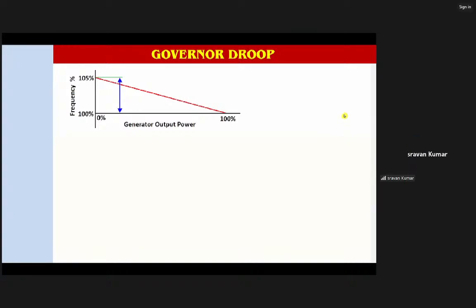Droop is basically this: whenever the machine unloads from full load to 0, maybe because of the opening of the generator circuit breaker, electrical output has become 0, and with steam energy still going into the turbine, the machine will accelerate, and finally it will stabilize somewhere. So in this particular graphic, you can see that suppose a machine output has changed from 100% load, say 600 megawatt, to 0. With that, there is a rise in speed of say 5%. From 3000 RPM, the speed has gone to 3150 RPM. So in that case, we say that this unit has 5% droop.